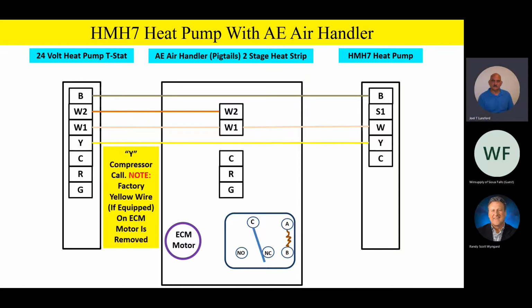Y terminal is going to go from the thermostat to the outdoor unit. This is your compressor call. You'll also notice on an AE air handler, you may have, now you don't necessarily have to have, but you may have a yellow wire if it's equipped from the factory. Go ahead and remove that yellow factory wiring, because we're going to be selecting speed taps on that ECM motor by way of our relay and some other functions. So go ahead and take that yellow factory wire off, because we're going to be using all the speed taps, or most of the speed taps, once we engage that relay.